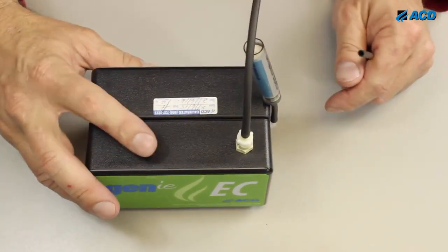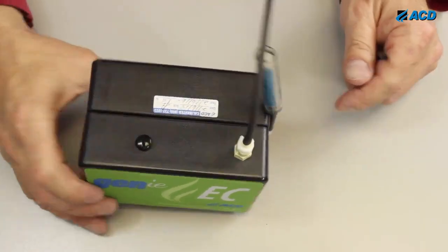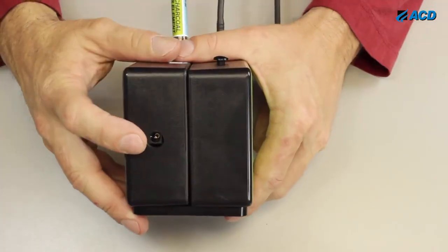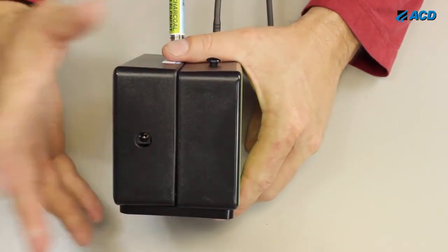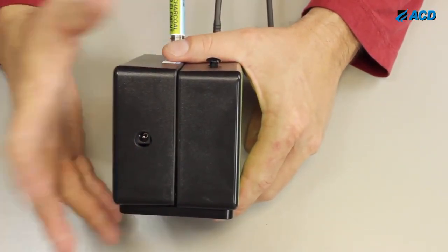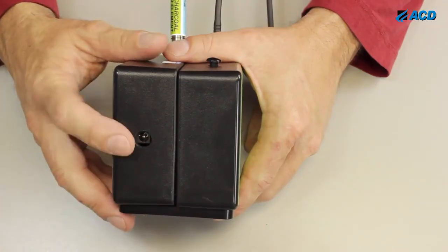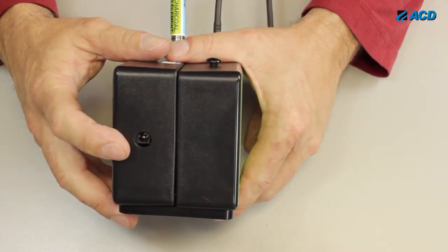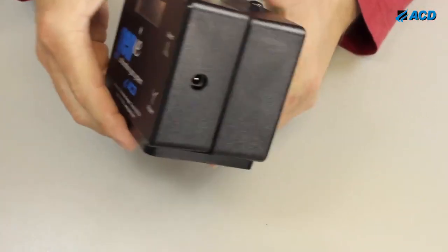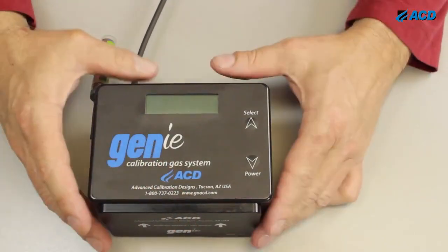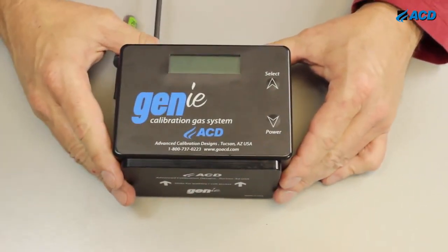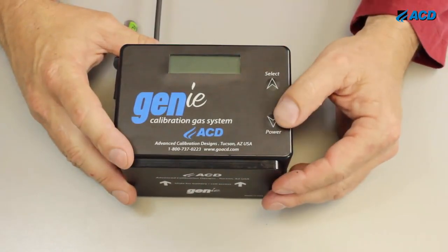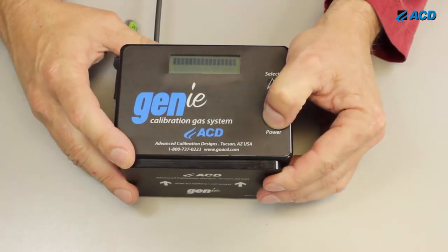This button here is to eject the generating cell when you're done. And over here we've got a continuous operation adapter port for people that do lots of calibrations in one spot, so you can just plug it into mains power and run the unit. Okay. So once we've got the generating cell inside of the instrument, what we want to do is turn it on. So to power up the unit, you press and hold the power button for 3 seconds.